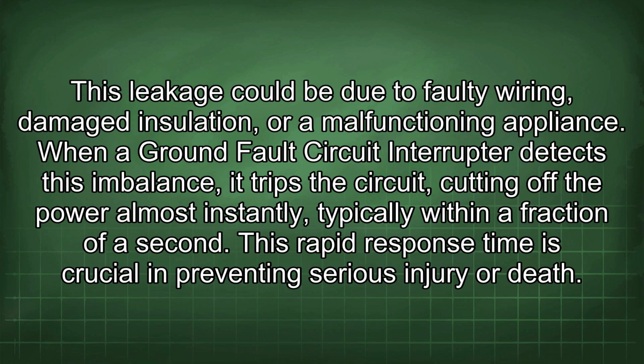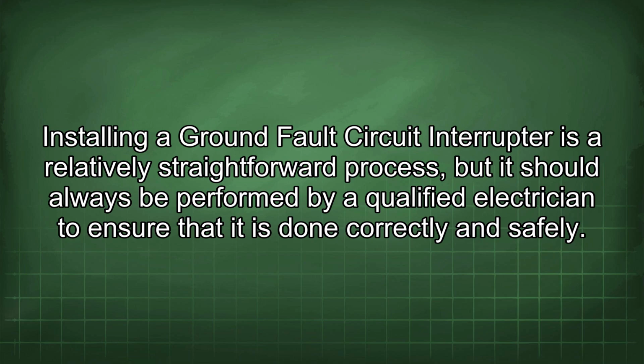When a ground fault circuit interrupter detects this imbalance, it trips the circuit, cutting off the power almost instantly, typically within a fraction of a second. This rapid response time is crucial in preventing serious injury or death. Installing a ground fault circuit interrupter is a relatively straightforward process, but it should always be performed by a qualified electrician to ensure that it is done correctly and safely.